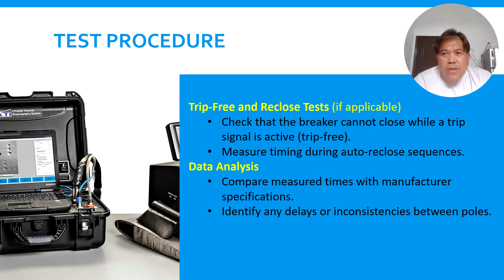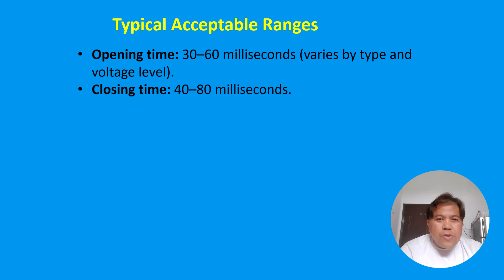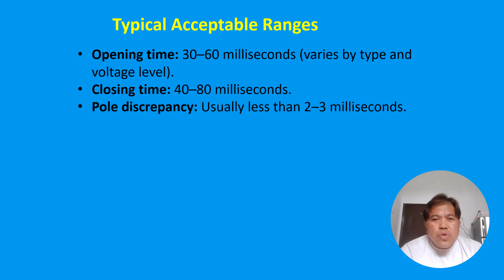Next, what is the typical acceptable range? This is very important. We need to identify our tolerance and acceptance values. Opening time is 30 to 60 milliseconds, varying by voltage level, because we have different voltage levels for our equipment and panels. Closing time is 40 to 80 milliseconds, and the phase discrepancy should be within 2 to 3 milliseconds during your timing.